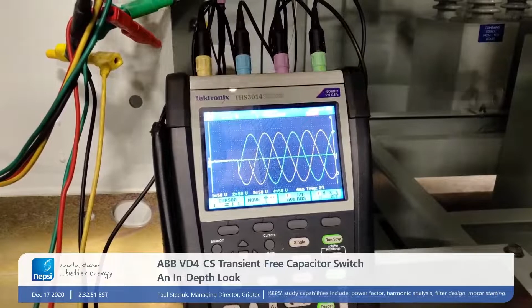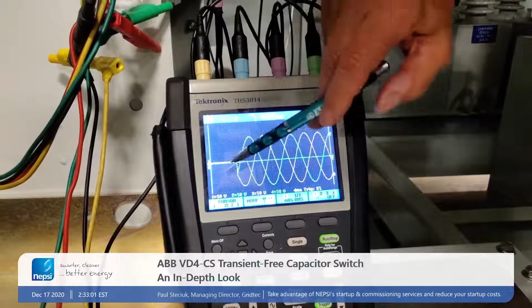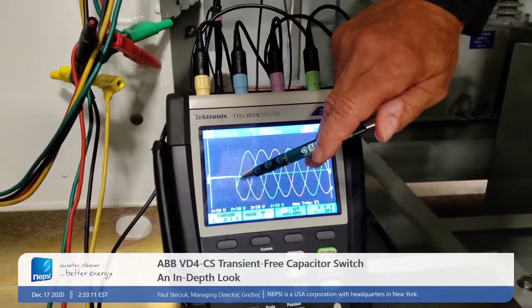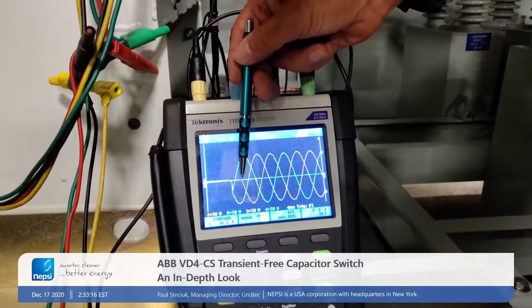You can see here that we have the blue and the magenta phase has closed. Blue and magenta is phase B, phase C. It closed when the B and C values were equal. In other words, 0 voltage closing. B and C are both closing at the same time. Thus, transient free between phases B and C. Then 90 degrees later, we have phase A closing.